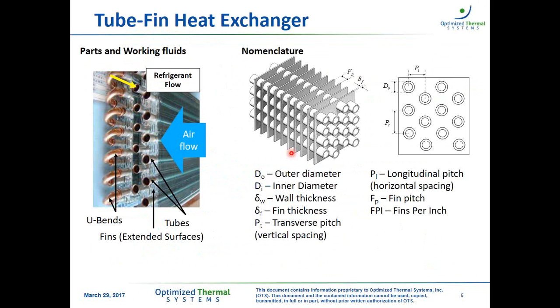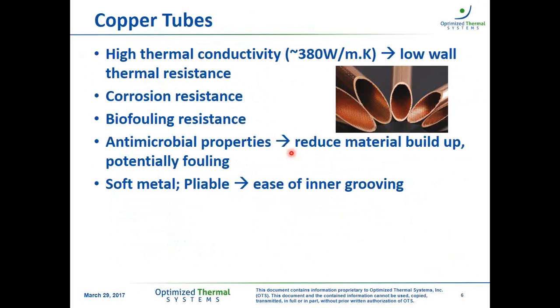Now, tube fin heat exchangers have 2 main parts. We have tubes and fins. So starting with tubes, in particular copper tubes, and why we are interested in having copper tubes in our heat exchangers, some of the interesting properties and characteristics. We have high thermal conductivity, which gives us low thermal resistance in the wall, thus facilitating the heat transfer between inner and outer fluid. We have additional advantages in terms of corrosion, biofouling, and antimicrobial properties, which from a heat exchanger context is more to reduce the material buildup and potential fouling that can block the fluid flow and therefore degrade the performance over time.